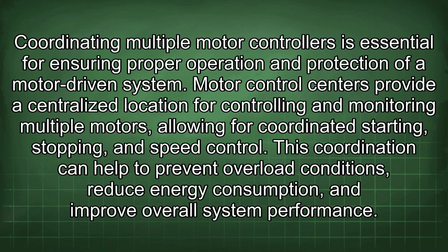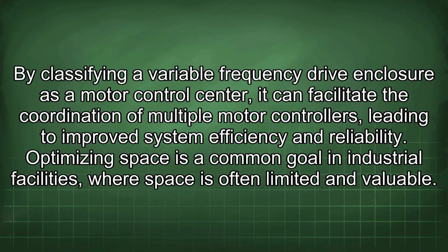Coordinating multiple motor controllers is essential for ensuring proper operation and protection of a motor-driven system. Motor control centers provide a centralized location for controlling and monitoring multiple motors, allowing for coordinated starting, stopping, and speed control. This coordination can help to prevent overload conditions, reduce energy consumption, and improve overall system performance. By classifying a variable frequency drive enclosure as a motor control center, it can facilitate the coordination of multiple motor controllers, leading to improved system efficiency and reliability.